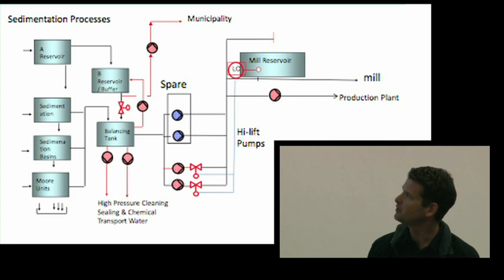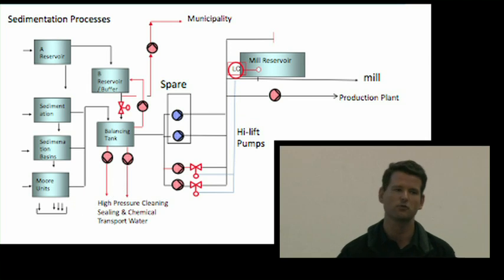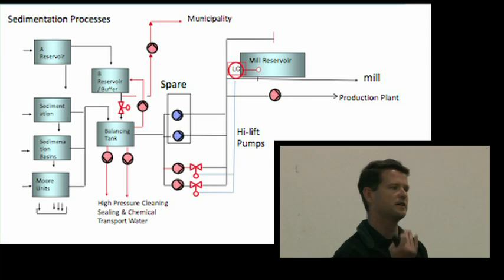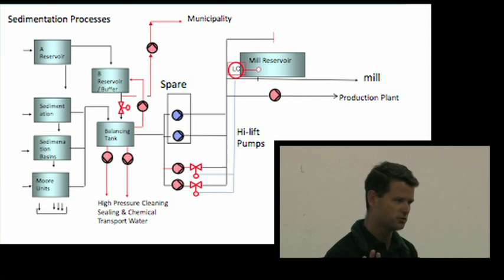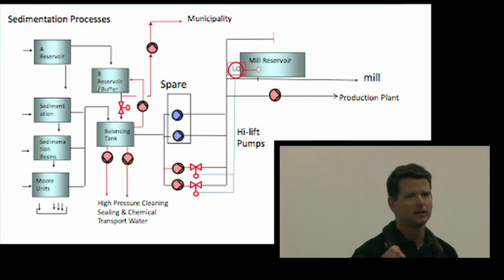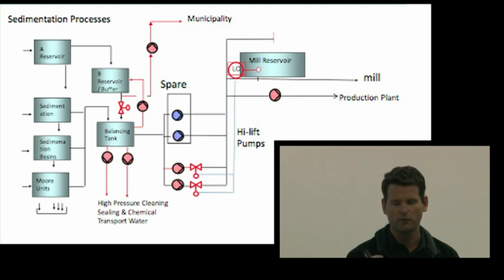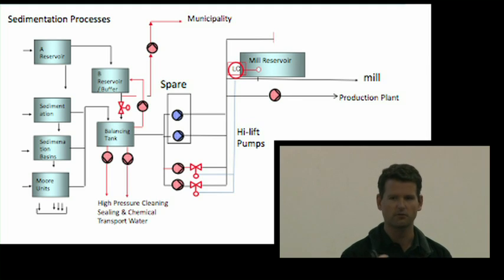Then, as I mentioned here, we had to put in a high pressure cleaning pump so that if we stop these pumps, they can do high pressure cleaning. And we had to put in a dedicated sealing water pump, which was also an energy saving, because now they got sealing water at 3 bar instead of 10 bar. But from a payback perspective, it wasn't great on energy efficiency.